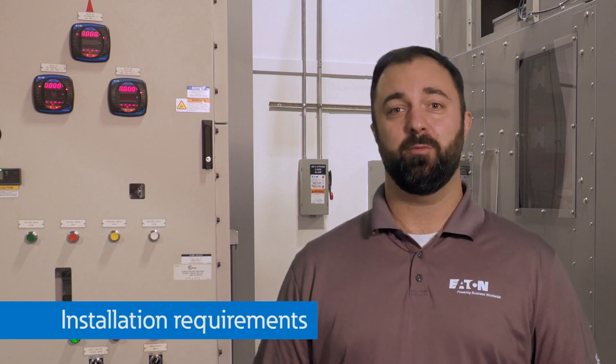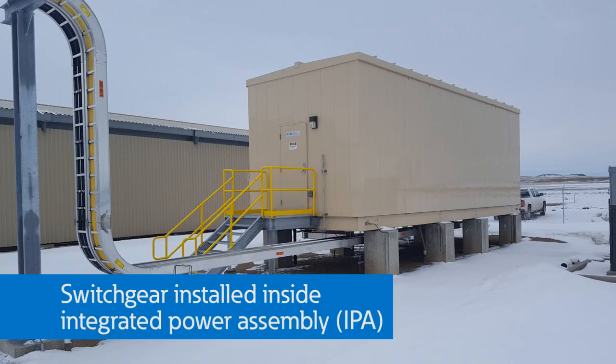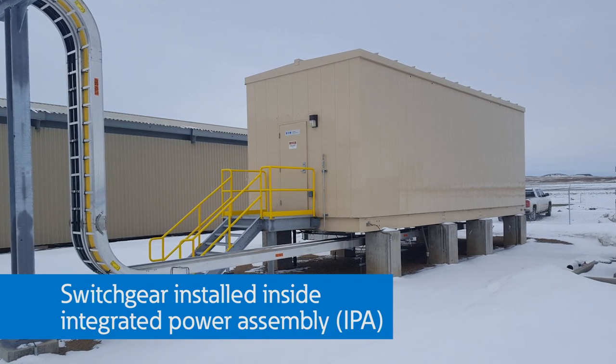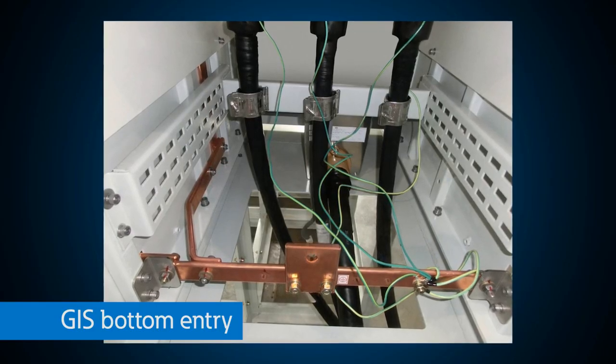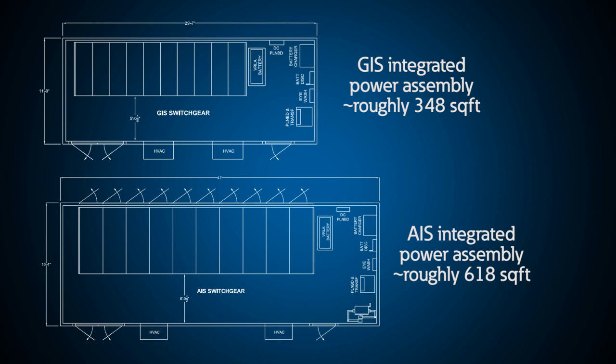We have discussed footprint and control power requirements. Now let's look further into installation requirements. Medium voltage AIS switchgear can have incoming voltage brought via cables or bus duct in the top, bottom, or side of the assembly. Whether your installation is in an integrated power assembly, over a cable vault, or installed on a concrete slab, an AIS lineup provides you with flexibility in your design. GIS switchgear is typically bottom entry for cabling and does not allow for traditional bus duct to be used. While AIS presents more incoming and outgoing connection options than GIS, GIS is front accessible, allowing the switchgear room to be decreased in size not only by having a smaller footprint but also by eliminating the need for rear access cable requirements.